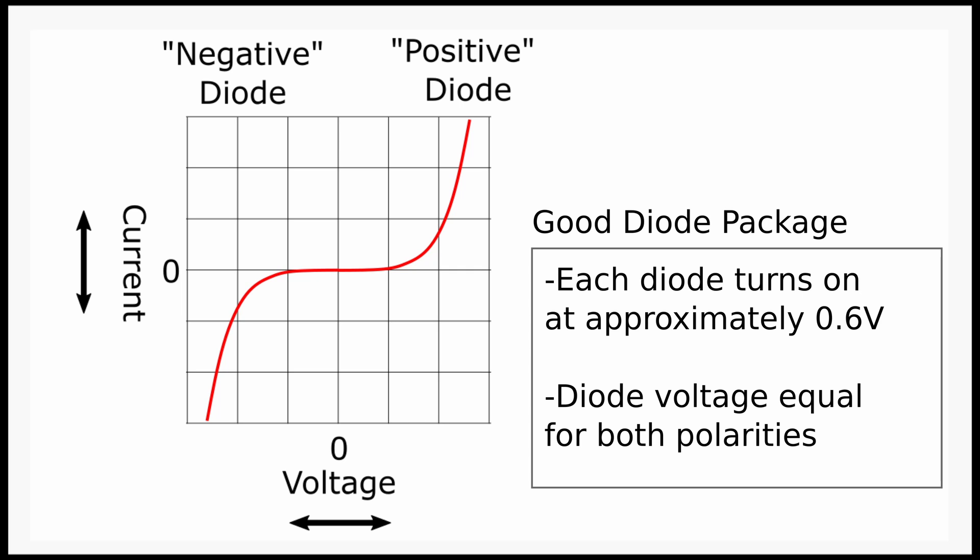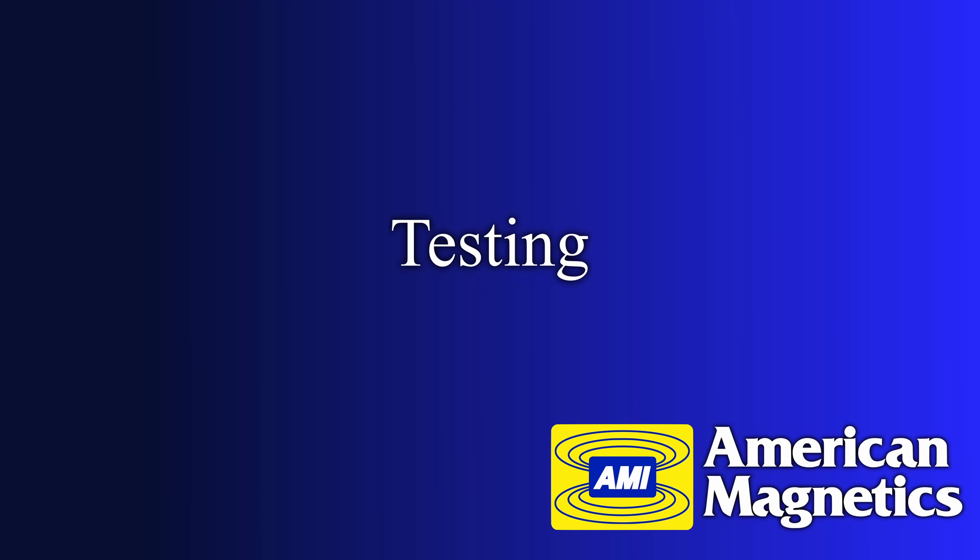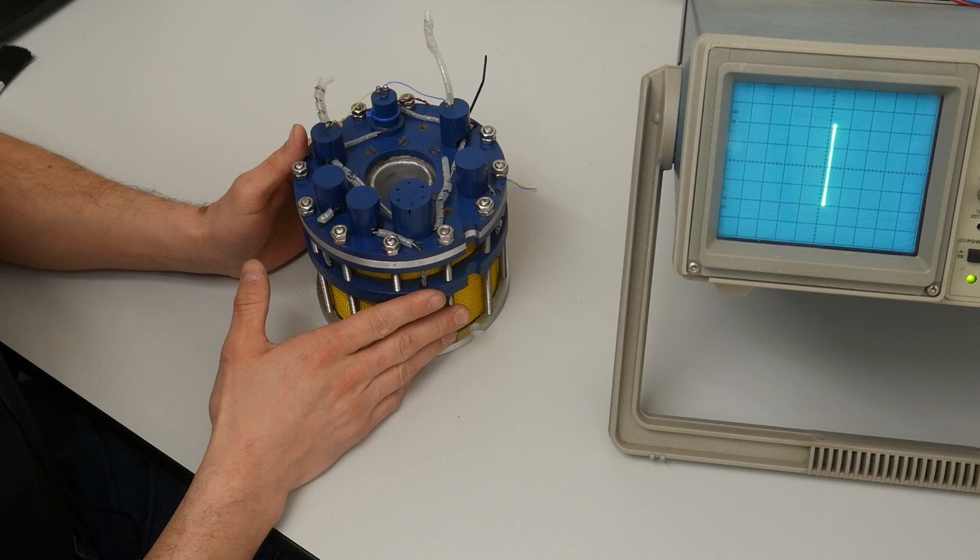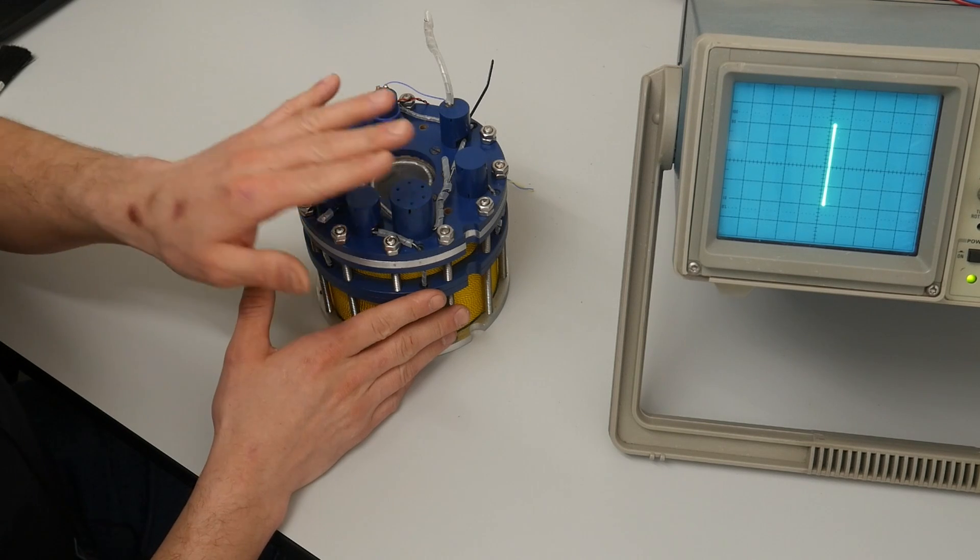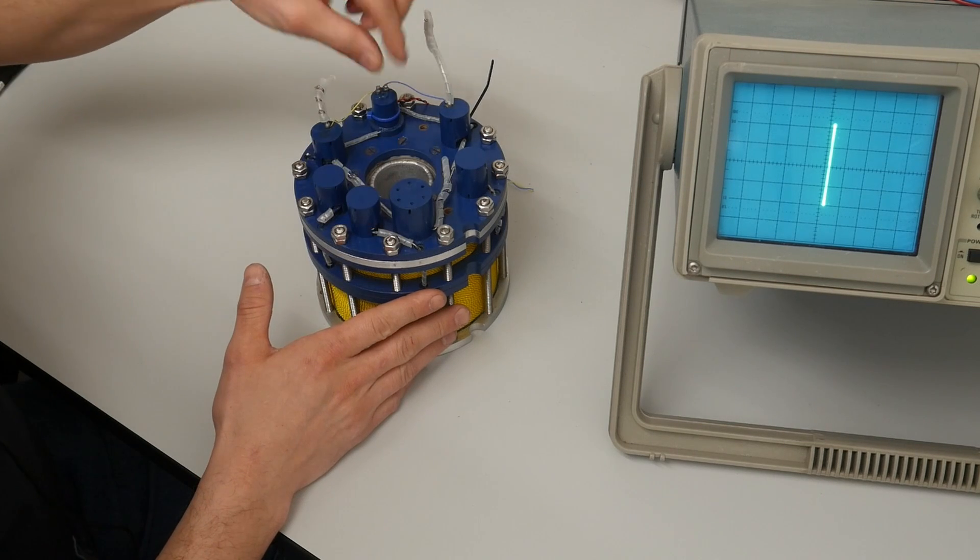Here's a 20-year-old magnet we had in storage. It has one diode and a persistent switch, and the rest of these are all lugs. The lugs are connecting all the different coils of the magnet together.